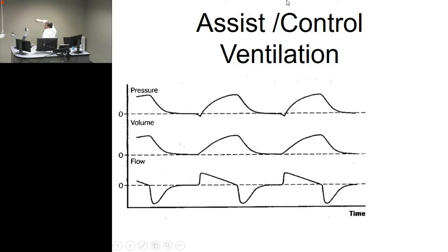And then for volume, we really want to see that our volumes are consistent and that we're not having a drop off or that it's not reading that we're missing some of that exhaled tidal volume. So if you were to see a curve go up here and then start to come down, and then right about that point it just drops, it goes straight down and it resets itself without actually coming out and finishing.